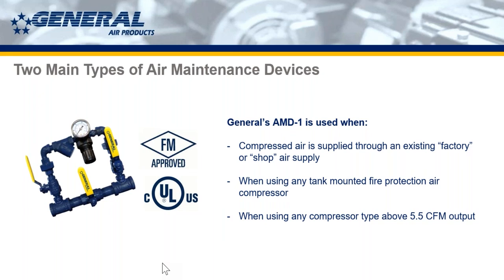And a lot of the ways to keep some costs down at that time was to run a line from the existing air supply to the fire sprinkler system. But these large air compressors, 100 horsepower, 200 horsepower, that supply compressed air for a variety of uses throughout a manufacturing facility, generally equate with very significant flow, and that is going to send that flow to the fire sprinkler system when a head goes off. And it's just going to keep running, and it's going to run a lot. And it can potentially prevent the dry valve from opening. So that's where the air maintenance device comes in, so that you limit that flow.